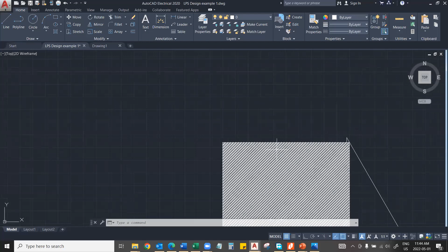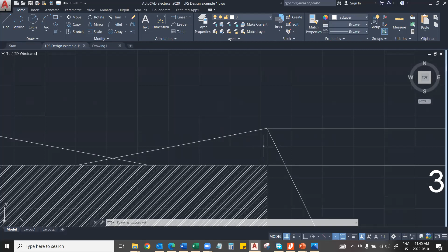When we are considering the protection towards these surfaces, your angle shall be considered based on the height from the bottom edge to the tip. So your angle will be more compared to towards the ground area - you have a small angle to the ground level here, and a higher angle towards this building's internal areas, because the idea of this is actually giving the idea of that rolling sphere which we considered with the step leader.